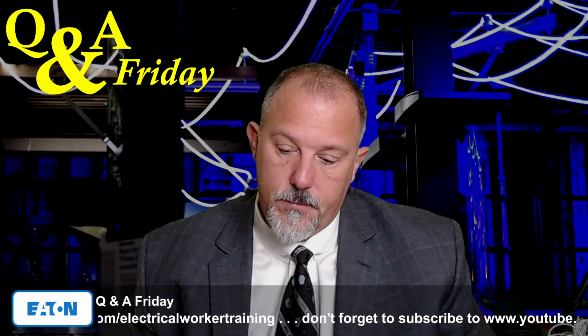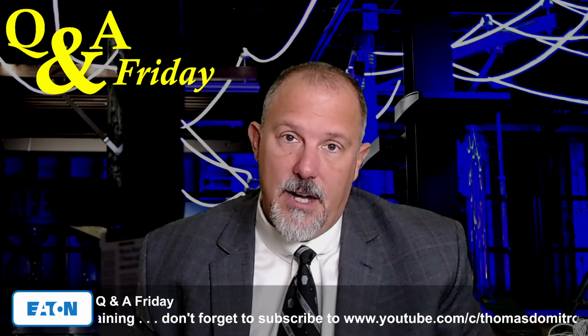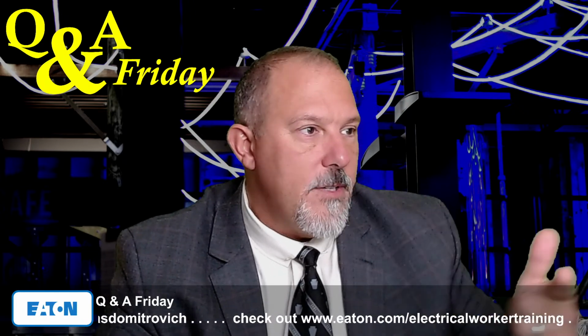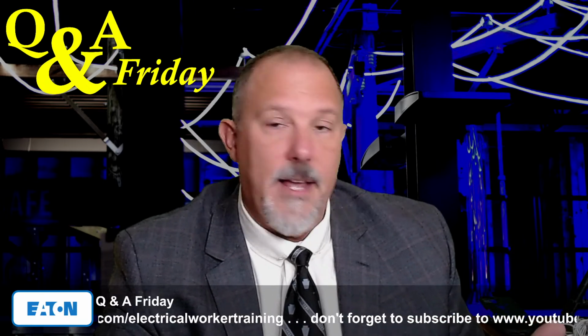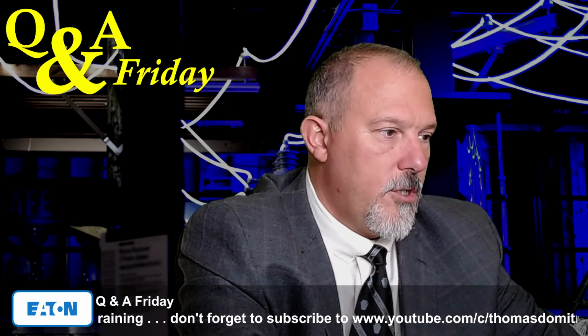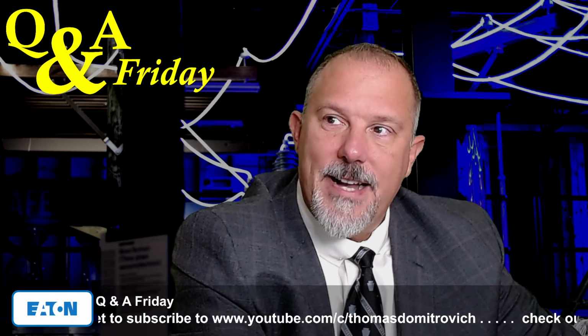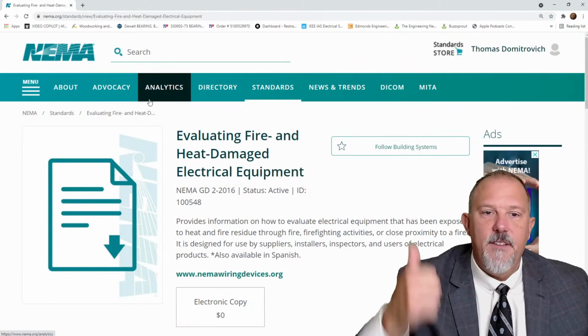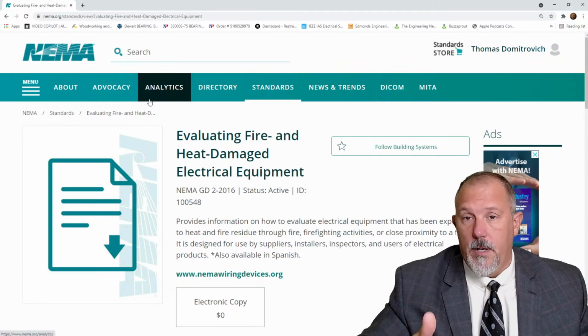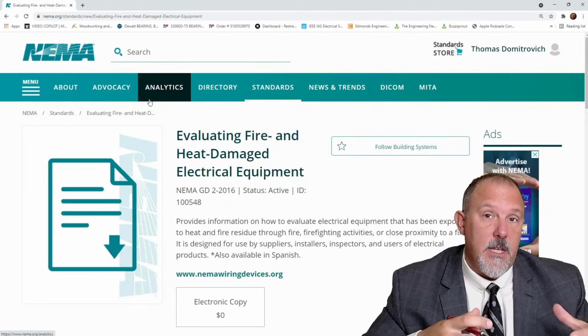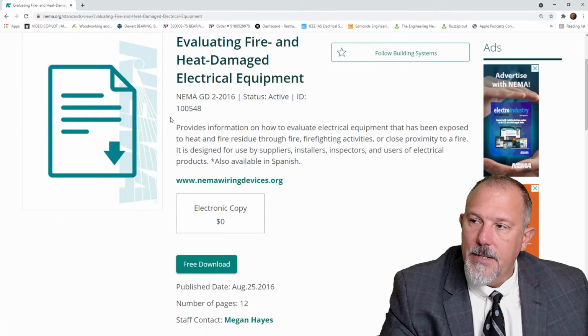So a meter center, if I look at the listing of a meter center, now he wasn't on the latest version of the code, which looks at whether you can and cannot recondition or refurbish it. So what I went to was there is a reference from NEMA on water damaged equipment, but also NEMA fire damage, I think it is. Yeah. So this was the reference that I sent him to: Evaluating Fire and Heat Damaged Electrical Equipment. Because his point was that with this cubicle, you can physically see that this equipment got a lot of heat. So what I did was I said, look, take a look at this Evaluating Fire and Heat Damaged Electrical Equipment. It's a free download.